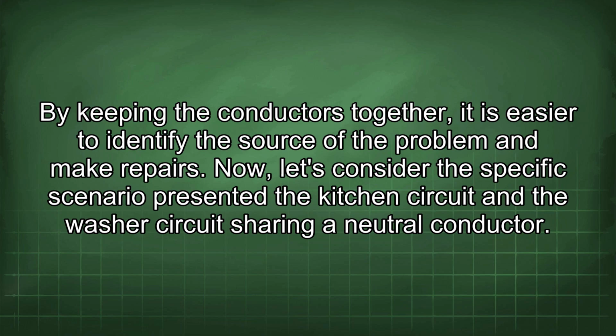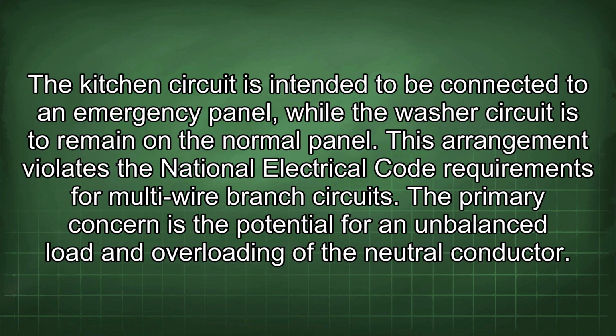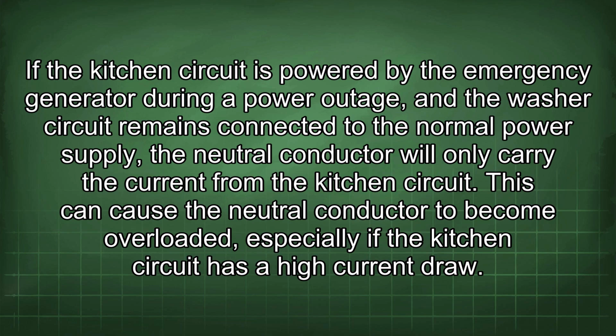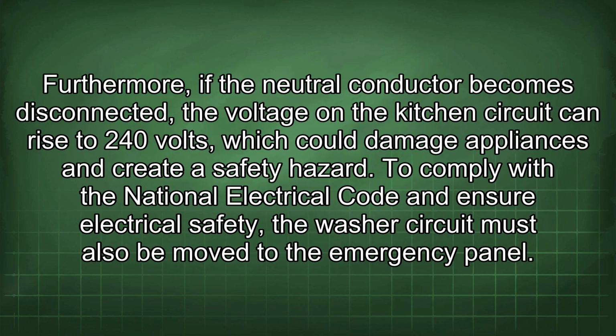Now let's consider the specific scenario presented: the kitchen circuit and the washer circuit sharing a neutral conductor. The kitchen circuit is intended to be connected to an emergency panel, while the washer circuit is to remain on the normal panel. This arrangement violates the National Electrical Code requirements for multi-wire branch circuits. The primary concern is the potential for an unbalanced load and overloading of the neutral conductor. If the kitchen circuit is powered by the emergency generator during a power outage and the washer circuit remains connected to the normal power supply, the neutral conductor will only carry the current from the kitchen circuit. This can cause the neutral conductor to become overloaded, especially if the kitchen circuit has a high current draw. Furthermore, if the neutral conductor becomes disconnected, the voltage on the kitchen circuit can rise to 240 volts, which could damage appliances and create a safety hazard.